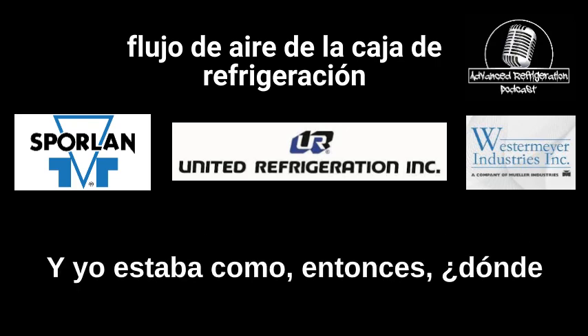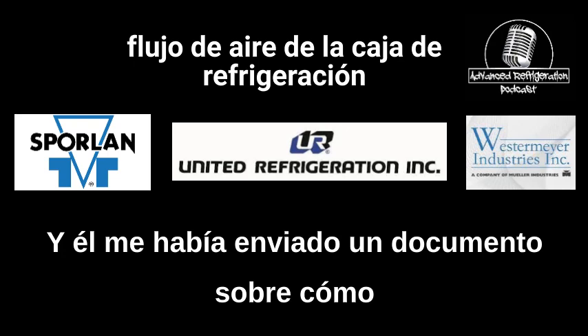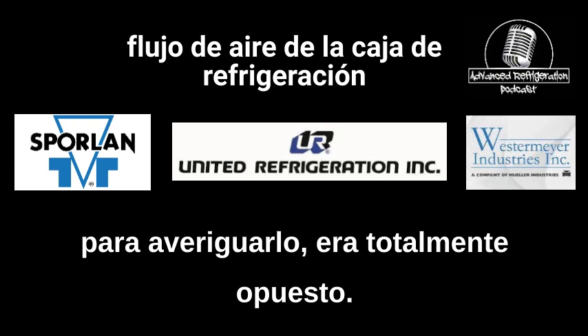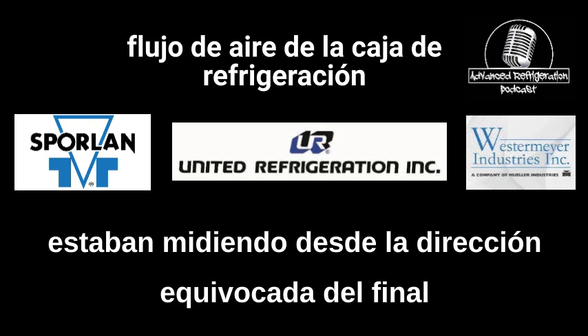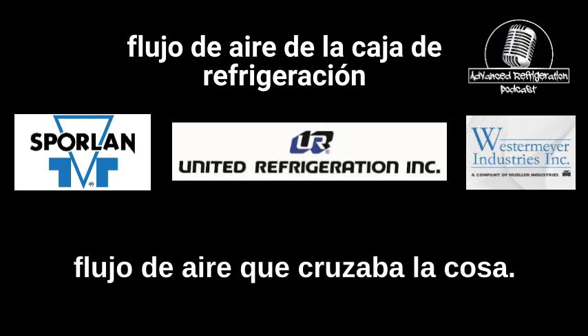And I was like, so where are these blades supposed to be? And he had sent me a document on how it was supposed to be set up, and come to find out it was totally opposite. Like they told him how far it needed to be, and they were measuring from the wrong direction of the end of the shaft. So it ended up throwing it way off, which essentially raised the TD because it was less airflow that was going across the thing.